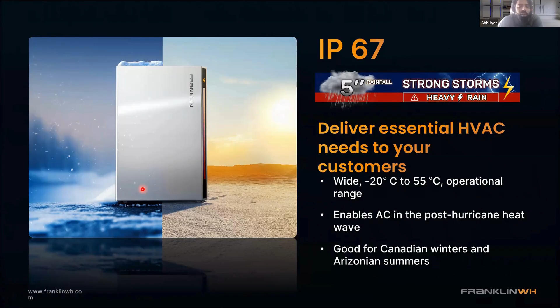If you've noticed this place has seen negative 20 degrees Celsius more commonly, or multiple days a year during winter, which does happen, you certainly want to find a spot indoors for those batteries. What you'd start observing at those low temperatures is that the batteries will see a reduction in charging behavior, so they won't be able to absorb 8 kW of power, especially at 0 degrees Celsius or negative 15 degrees Celsius. There's no impact to the discharge capability though, the batteries will still put out 10 kW, 11.5 kW continuous power output, even at negative 19 degrees Celsius. But if temperatures fall below negative 20 degrees Celsius, the batteries will automatically shut down for safety, and will automatically come back online once the cell temperatures recover within range. So no intervention is necessarily required by the installer or homeowner for the battery to deliver, especially during winter.